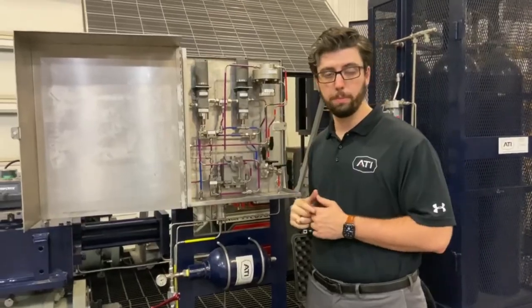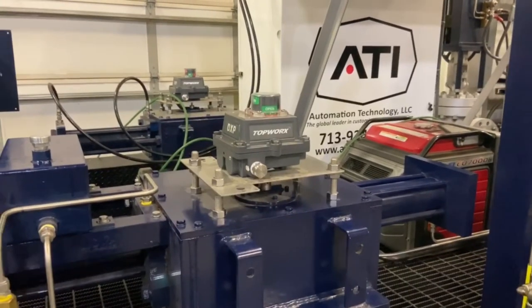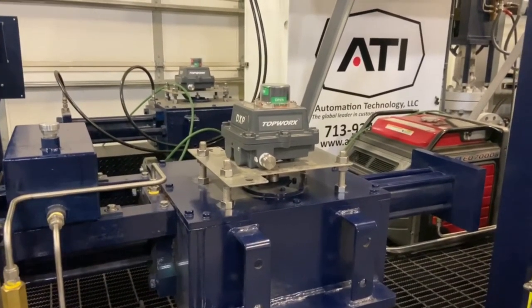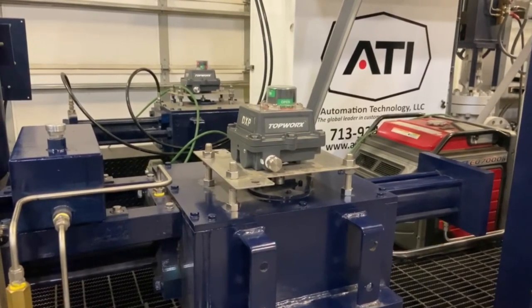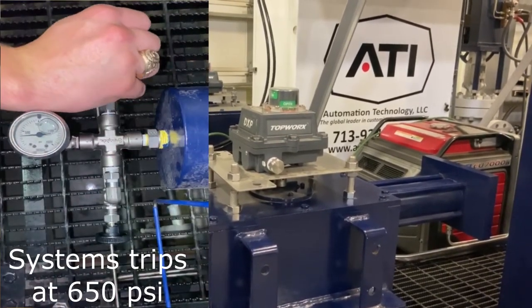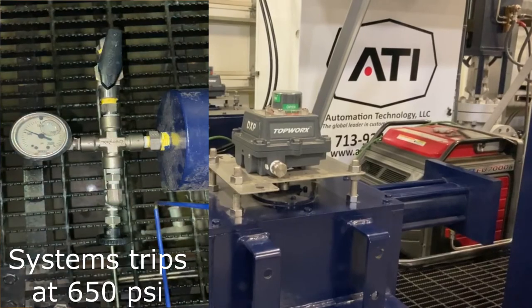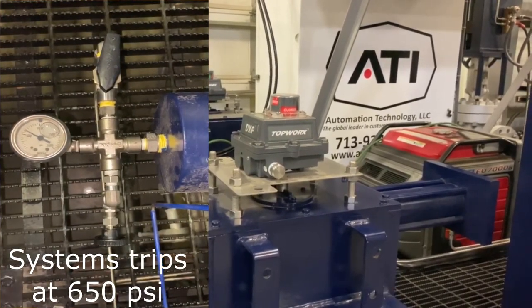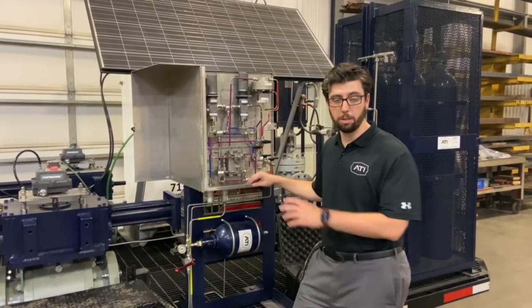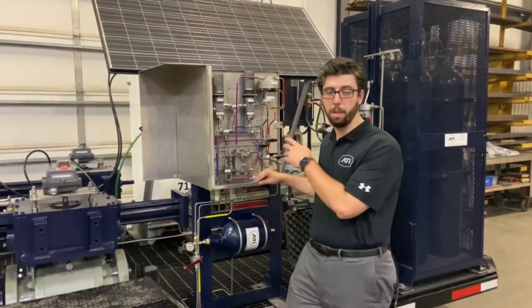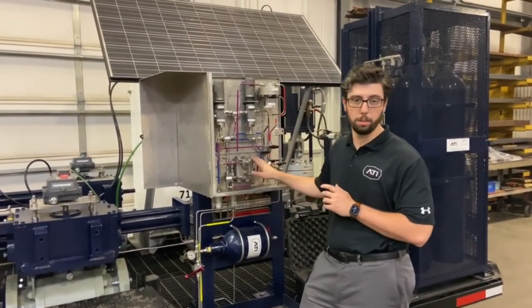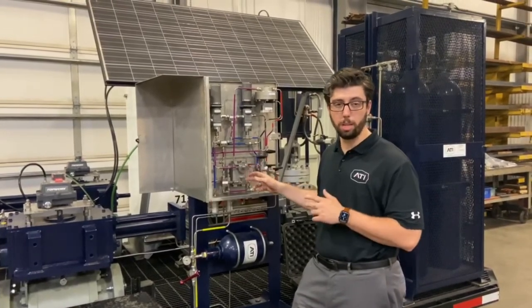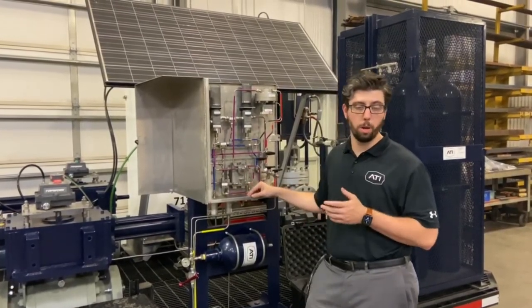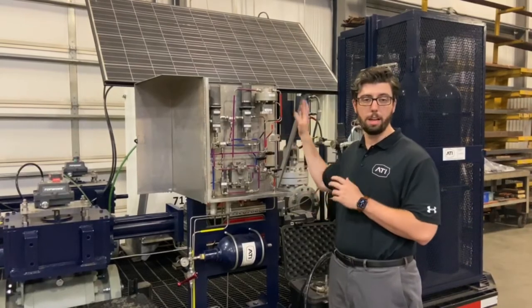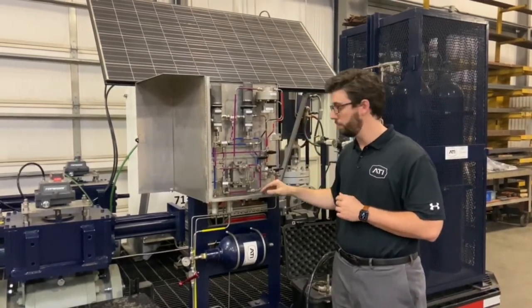Next, what we're going to do is show off our high pressure trip system. Here we are going to demonstrate our high pressure trip system for overpressure protection. Now that our actuator has fail closed from our high pressure trip system, I'm going to demonstrate using our poppet block in order to locally open the valve before going into the demonstration of our line break trip system.